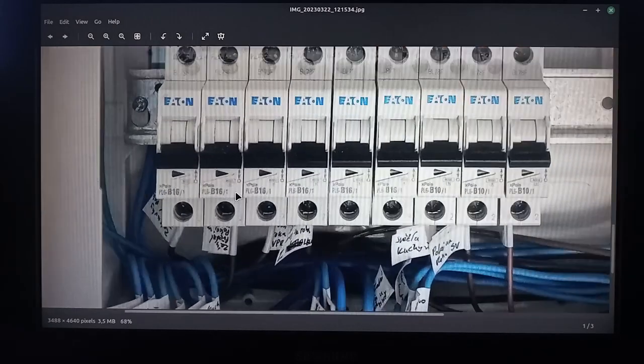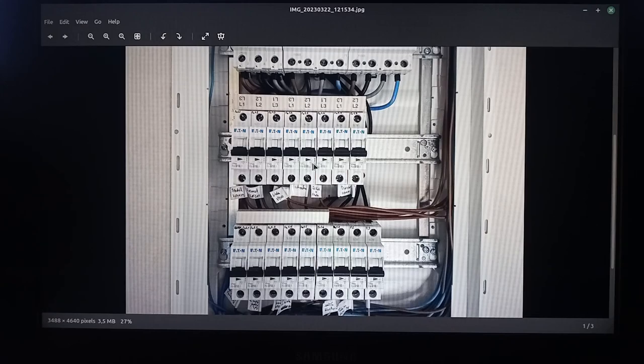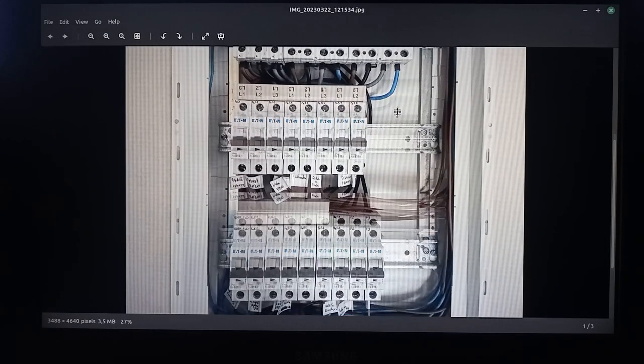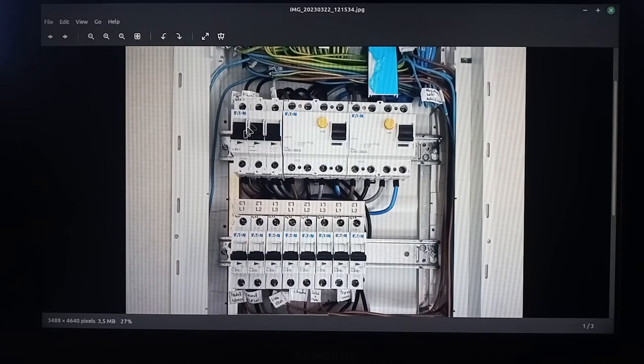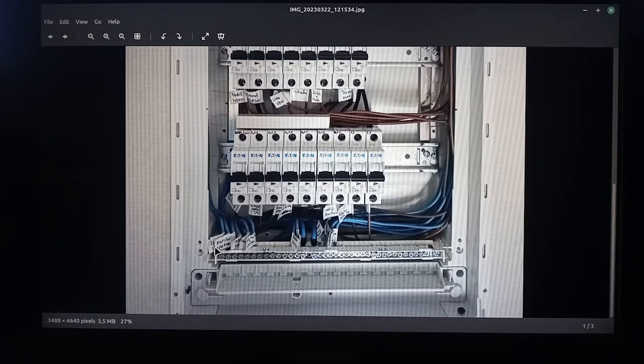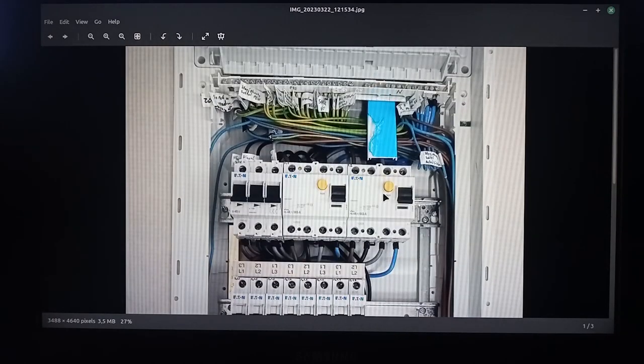You can see some tags where things are marked. There are some 16-amp switches and some 10-amp switches. That photo was taken when it wasn't finished yet. Right now there's power in there but the place is still under construction, only being used for construction purposes. You can see there are two RCDs — this one is for the kitchen, that's the top row, and this one is for the rooms, that's down here. This is the main switch, it has no characteristics, it's just a switch. Up here in this mess you can see where the cables come in. This is your PE rail, this is your N rail, this is your N1 rail — that's for the first RCD breaker — and your N2 rail is for the second one.